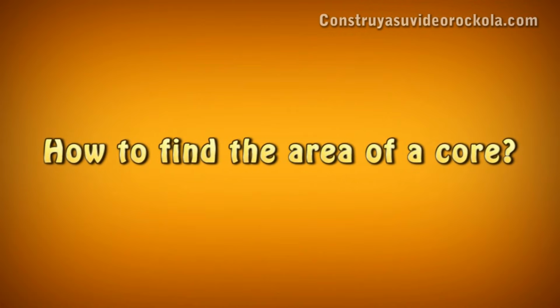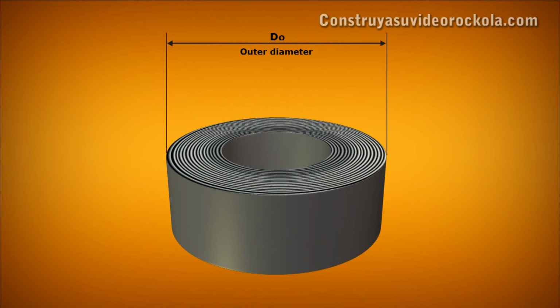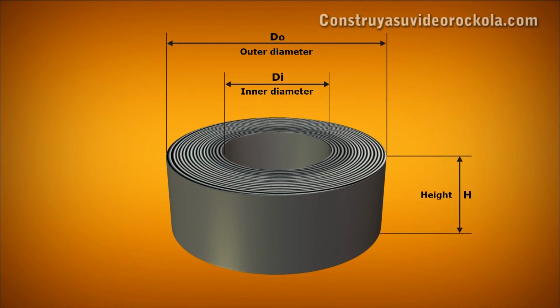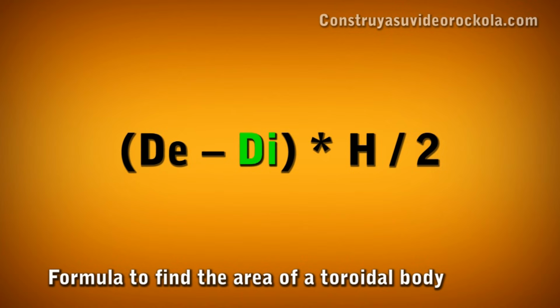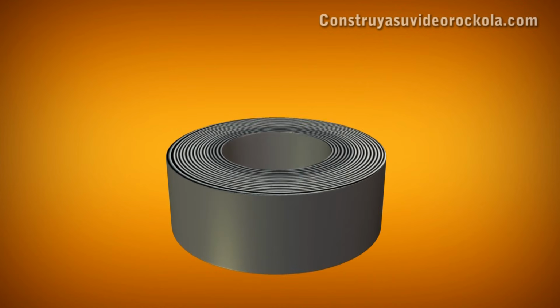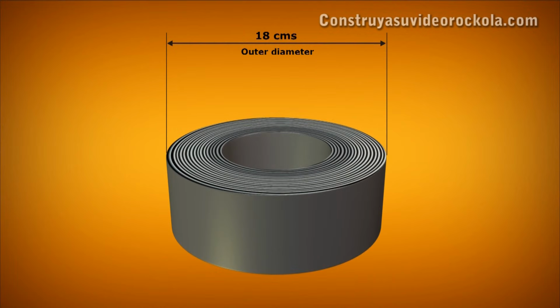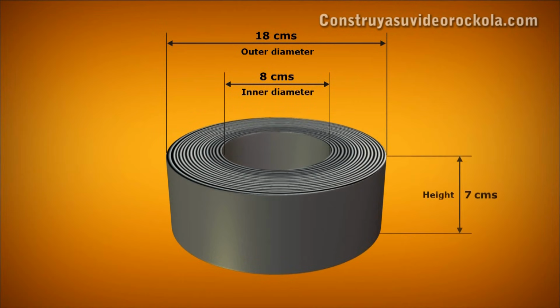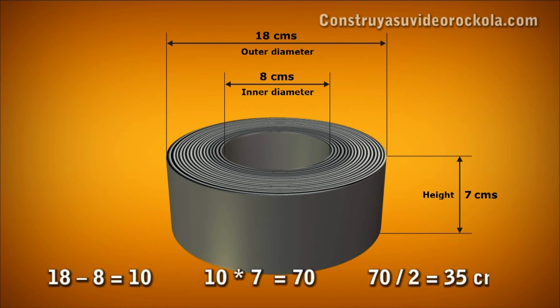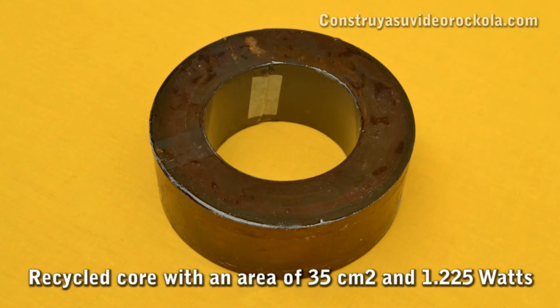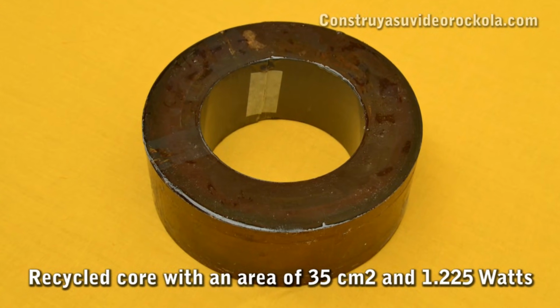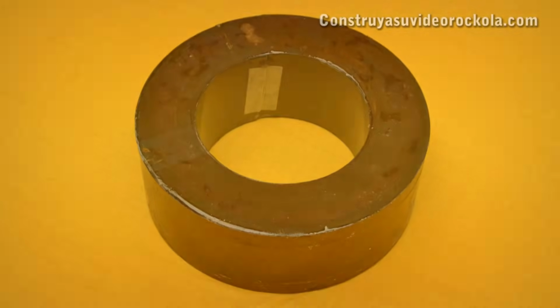How to find the area of a core? Very easy. We measure the outside diameter, the inside diameter, and its height. From the external diameter, we subtract the inner diameter, the result is multiplied by the height and divided by 2. In this case, we have a core of 18 cm of external diameter, 8 cm of inner diameter, and a height of 7 cm. 18 minus 8 equals 10. 10 multiplied by 7 equals 70. 70 divided by 2 equals 35 cm squared, which is the area of the core. A core with an area of 35 cm squared is capable of supporting up to 1225 watts.